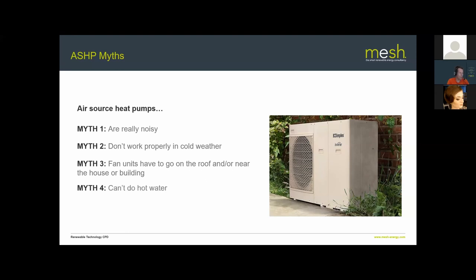Myth four: heat pumps can't do hot water. Not true — heat pumps will quite happily produce domestic hot water. Newer heat pumps with newer refrigerants can reach up to around 55°C, and most produce hot water to around 45°C. You slightly increase the size of your domestic hot water cylinder to compensate. What you can't do is replace a combi boiler directly — there's no air source combi equivalent, so you will always need a hot water cylinder.